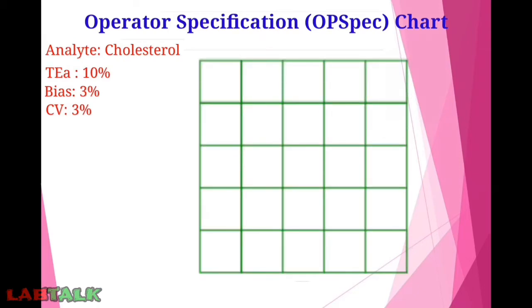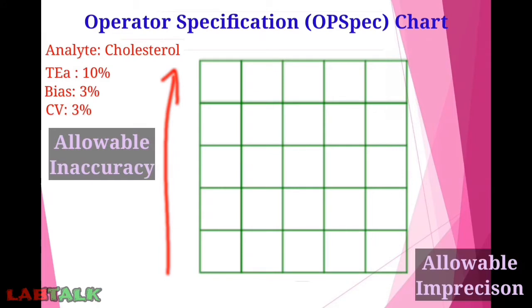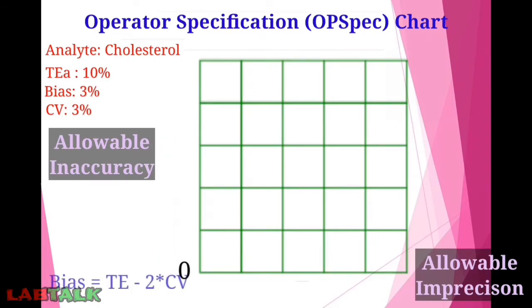Again using the cholesterol example with total allowable error 10%, bias 3%, and CV% 3%: consider a table with five columns and five rows as a grid. On the x-axis is allowable imprecision and on the y-axis is allowable inaccuracy, with the intercept at zero. First, consider the allowable inaccuracy on the y-axis — if CV% is zero, bias ranges up to the total allowable error, so we plot the point 10 on the y-axis.